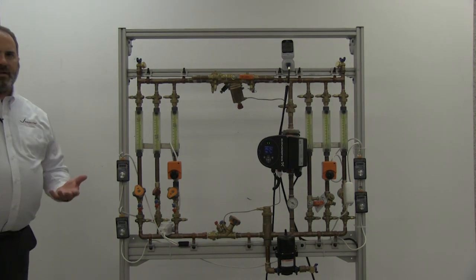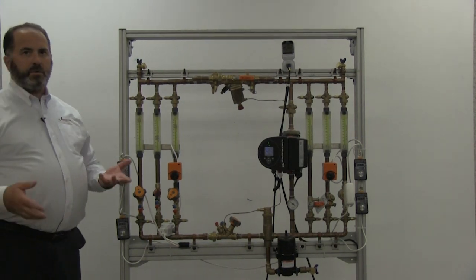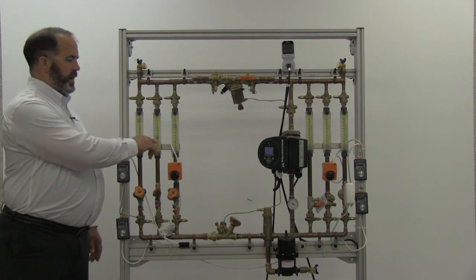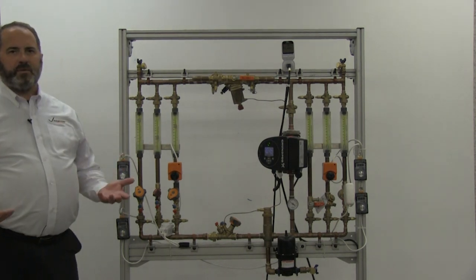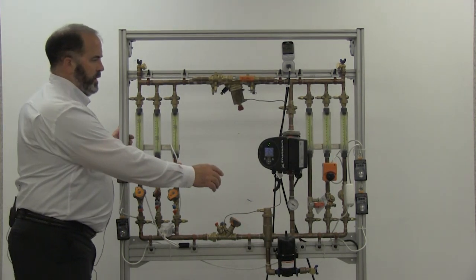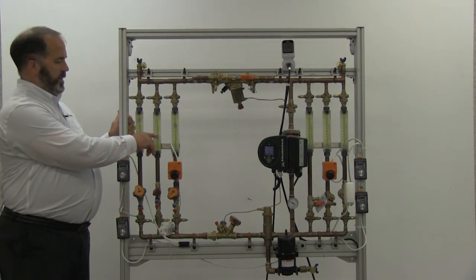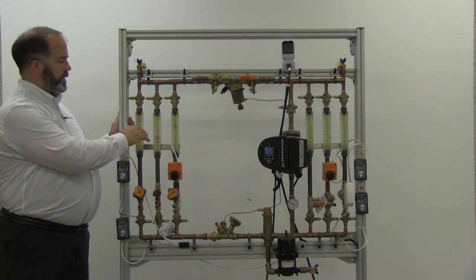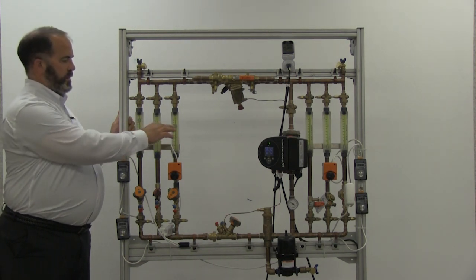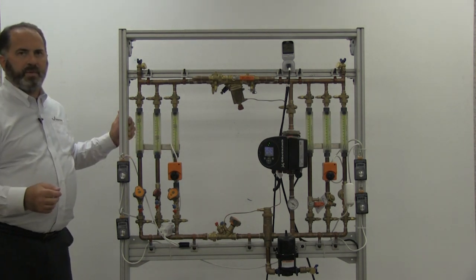Now let's go back to the unbalanced case and use pump optimization to at least get our index coil to the point that it needs to be for design flow. So right now I'm back in the unbalanced state. So I'm overflowing by about 10-15% on the index coil, and then much greater amounts on my other two coils within my branch.